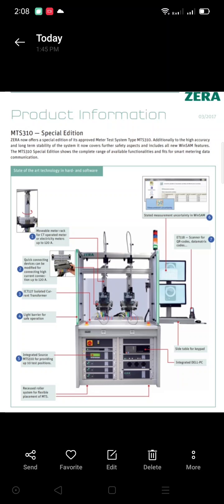And coming to the specification of the communication, what are the communication facilities that can be tested by using this equipment. Basically, the smart meter can be tested on its optical port, how the optical port behaves with the communication equipment. This is based on the standards IS 15959 and 16444, and we can also test the communication capability of the RF port with the equipment. Then we can perform the functional tests such as A30 of IS 15959 part 2 and table 29 of IS 15959 part 3.